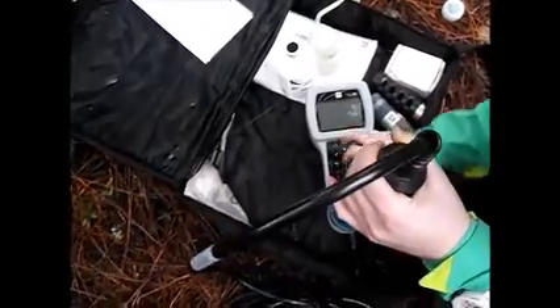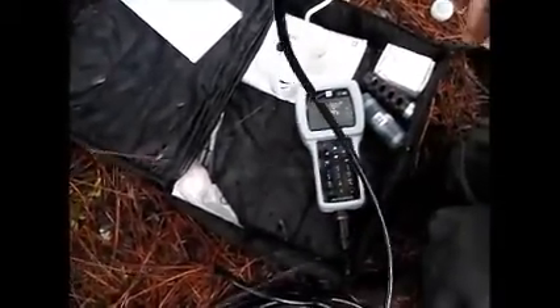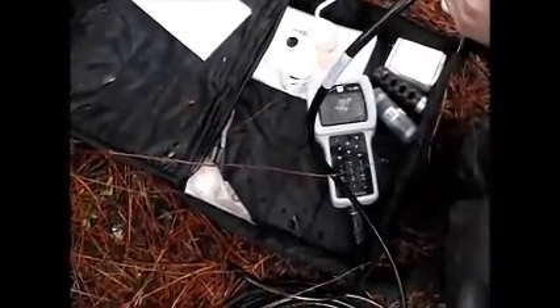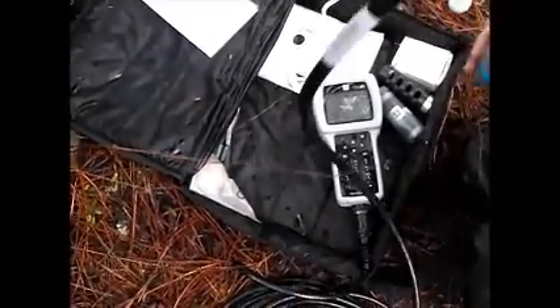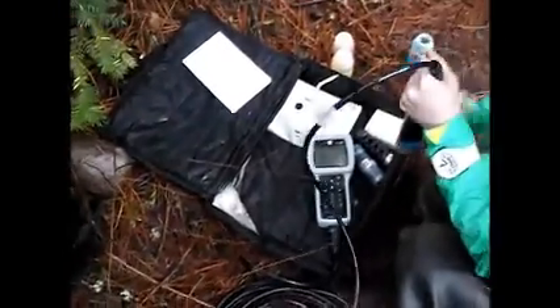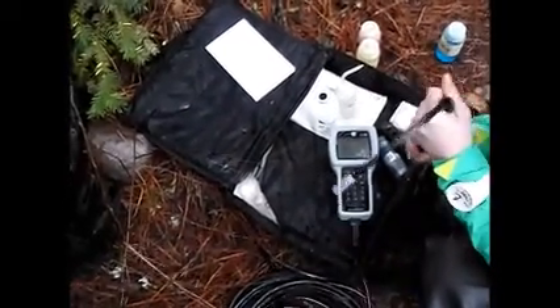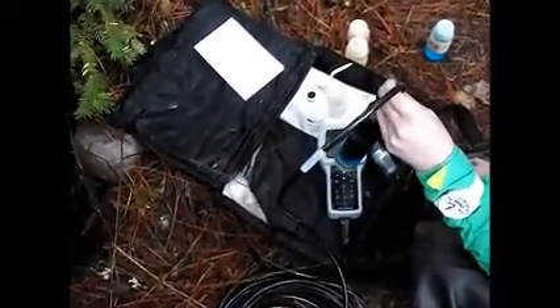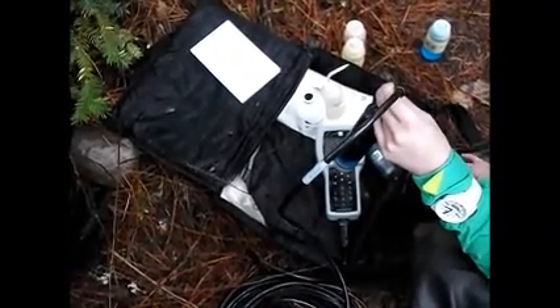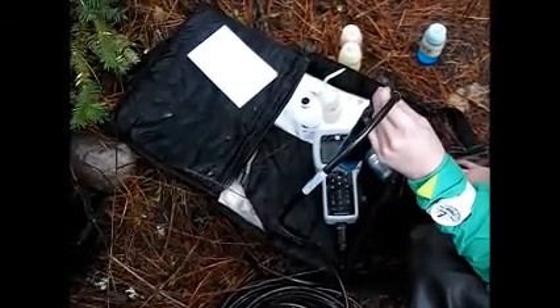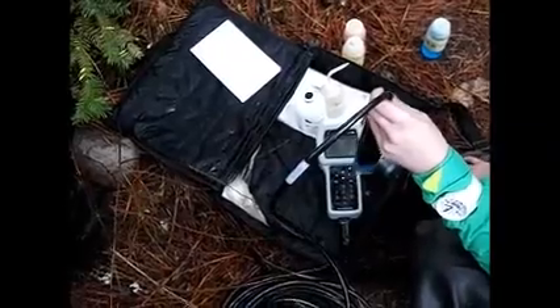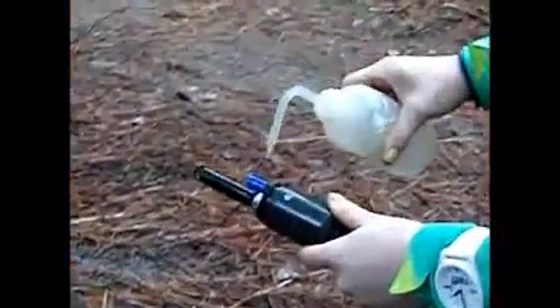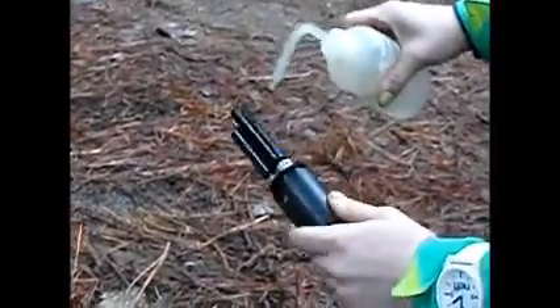Then you'll want to pour enough standard into the plastic cup to fill it about 3/4 full. Screw it onto the probe, then use the navigation menu to select calibrate, pH, and then enter 7. Wait until the digital readout stabilizes and then accept the reading. Then repeat these steps for pH 4 and 10. It's also a good idea to rinse the probe off with distilled water after each pH calibration.